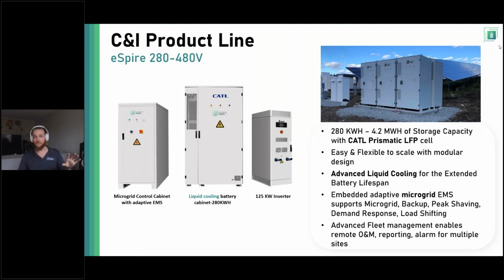This first product we're going to talk about is called the eSpire 280. It stands for 280 kilowatt hours of energy storage. It's essentially these 3 pieces of equipment: a 280 kilowatt hour battery cabinet in the center, on the right-hand side a 125 kW 480 volt inverter, and on the left-hand side, that's really our special sauce - the microgrid control cabinet. That's the brains of the system, handling the system level BMS.